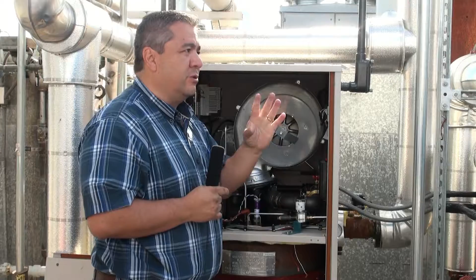It sits like this, so it doesn't matter where you end up. But the problem is that if it doesn't arc, it doesn't spark, and it doesn't arc because there's a carbon buildup on the inside of the assembly. So you get the metal brush, just like a baby bottle cleaner, and then you put everything back together again, and put all the piping back together again, and it'll take off on its way. Are these burning natural gas or waste gas?